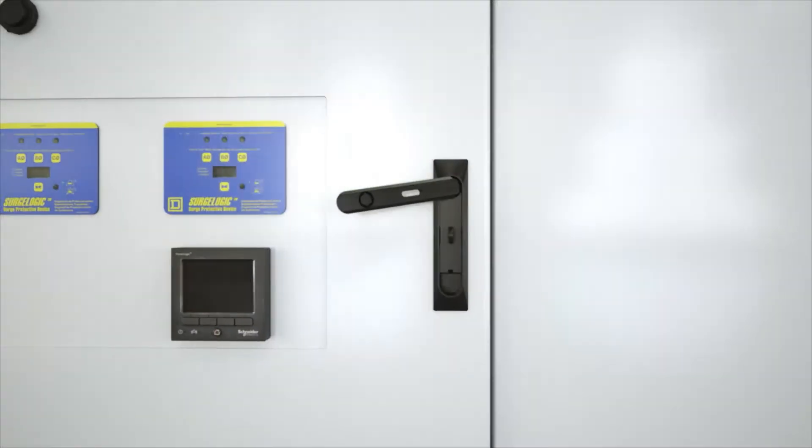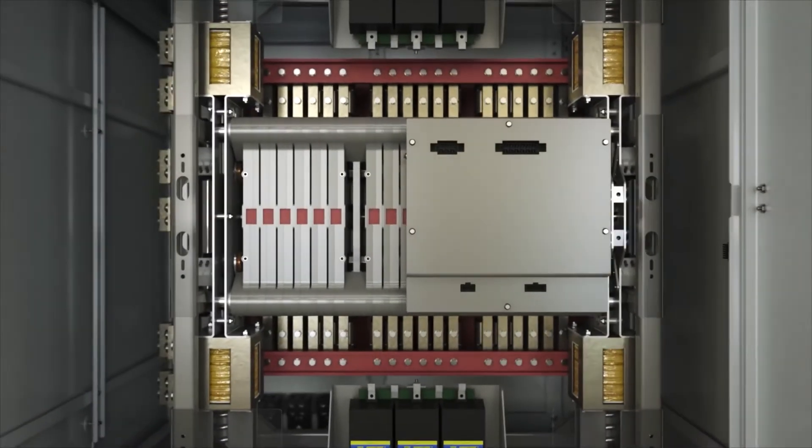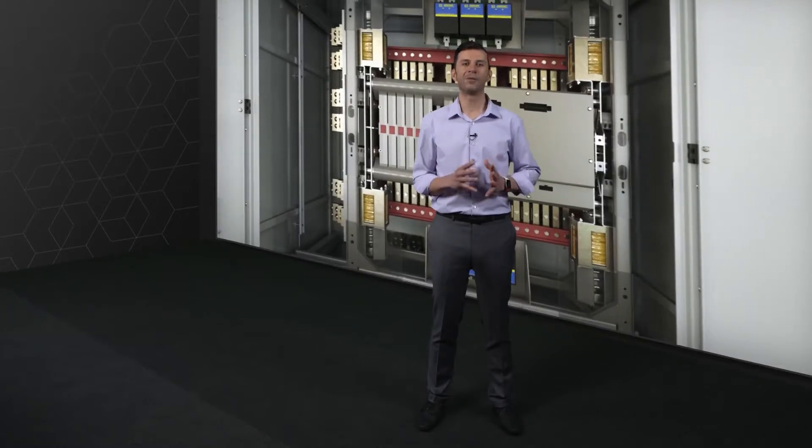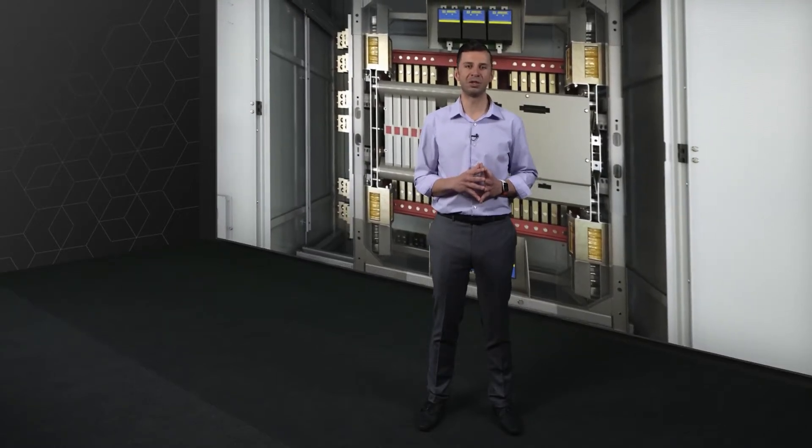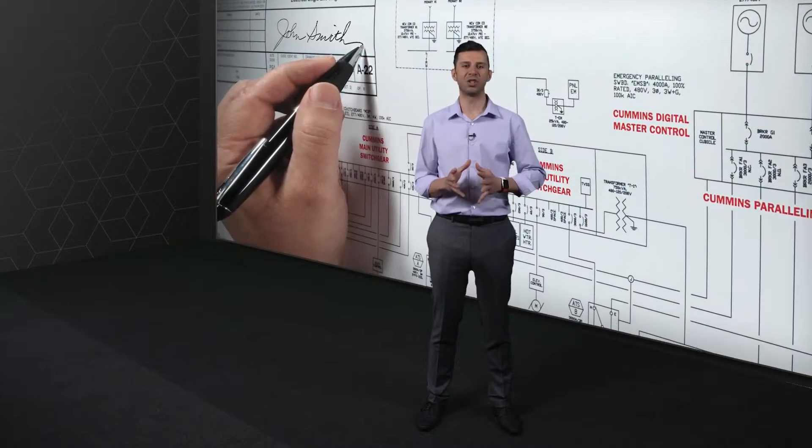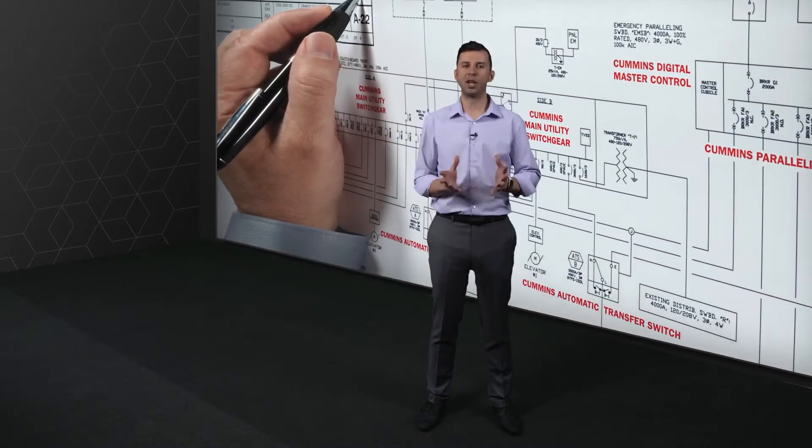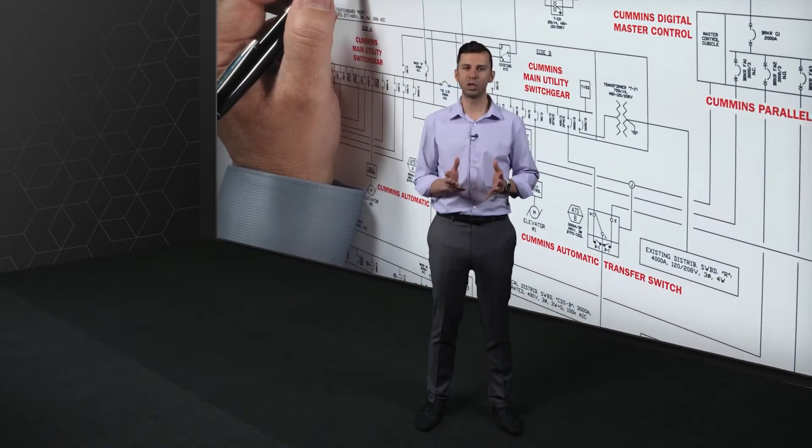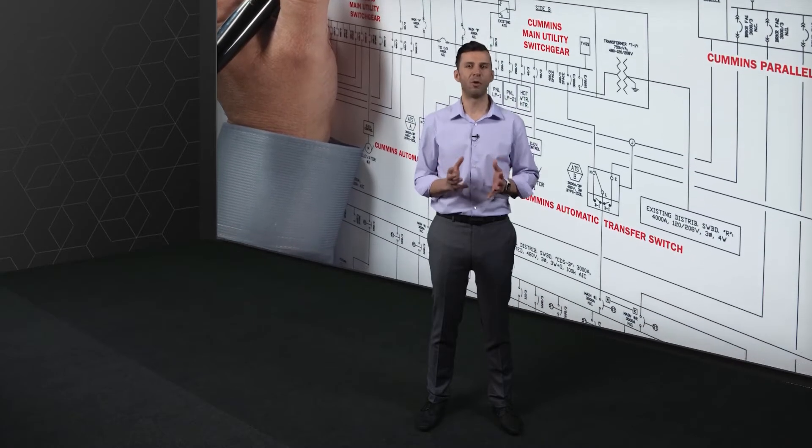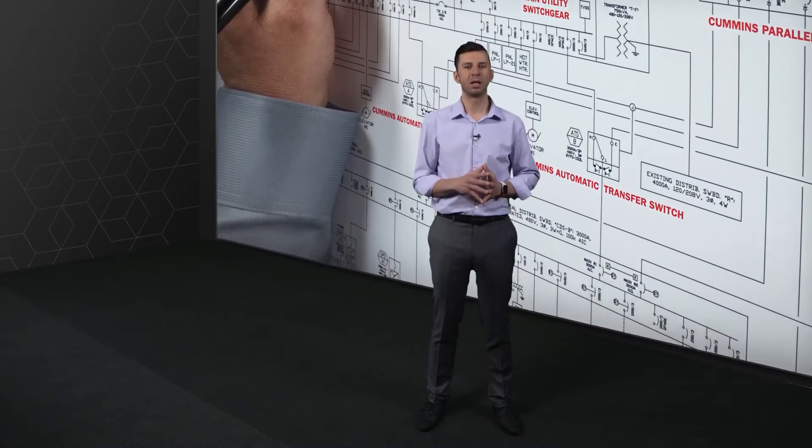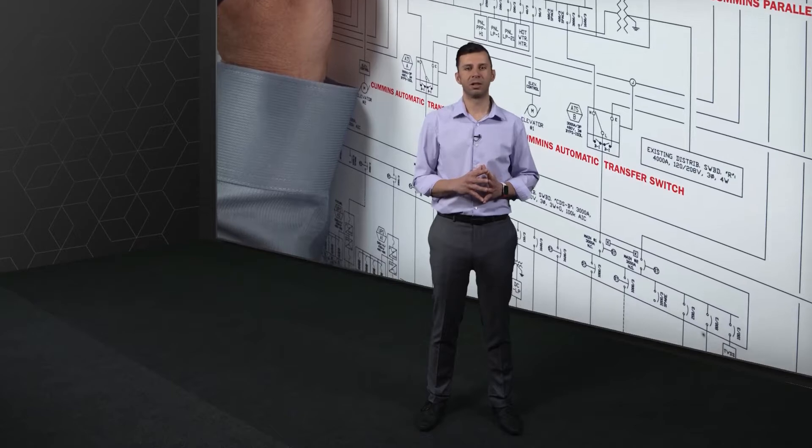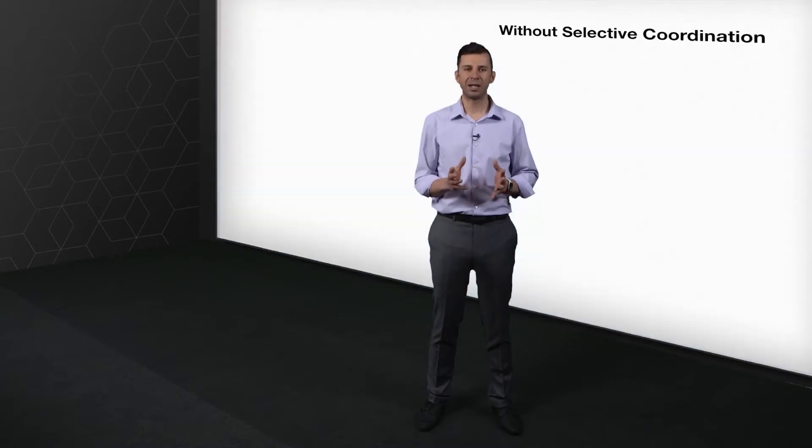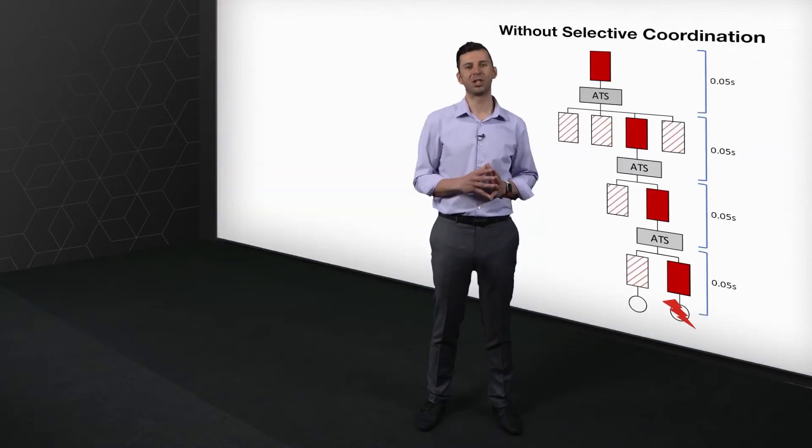And what does that superior time-based WCR mean to you? From speaking to thousands of consultant engineers, we learned that some of the major challenges during the design phase range from unknown switchgear switchboard OEMs and therefore unknown breaker selections to unknown available fault current, as well as challenges arising from selective coordination.